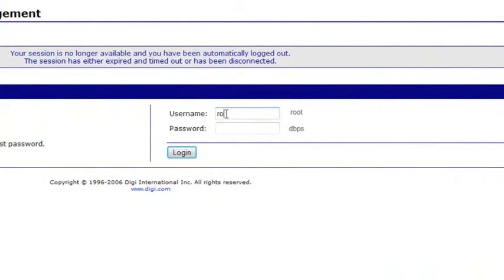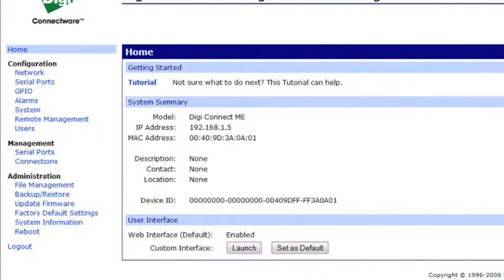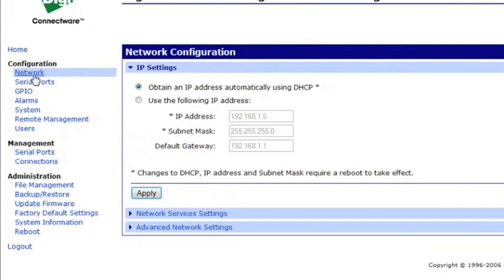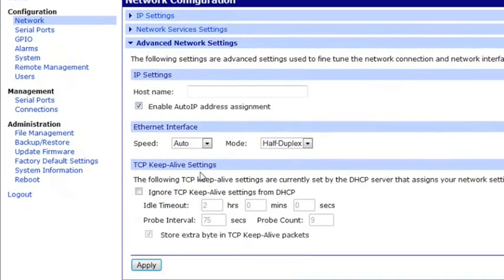You'll put in the username of root and the password of dbps. Once you're on this screen, on the left you'll see Network under the Configuration. Select that. Make sure Obtain IP Address Automatically Using DHCP is selected. Now I want to click on the Advanced Network Settings.